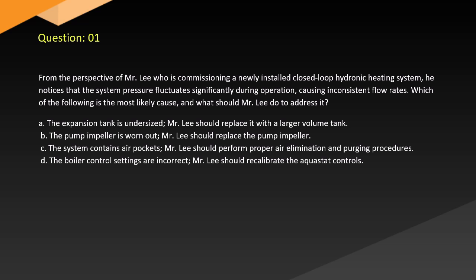A. The expansion tank is undersized. Lee should replace it with a larger volume tank. B. The pump impeller is worn out. Lee should replace the pump impeller. C. The system contains air pockets. Lee should perform proper air elimination and purging procedures. D. The boiler control settings are incorrect. Lee should recalibrate the aquastat controls.